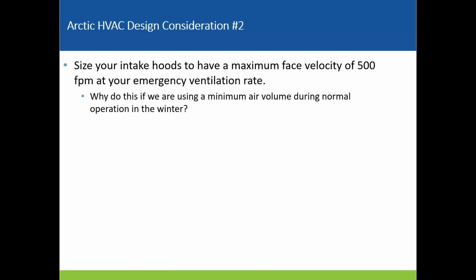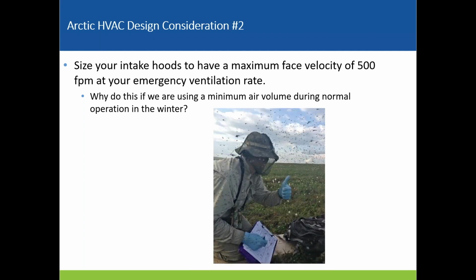So another Arctic design consideration, size your intake hoods to have a maximum face velocity of 500 feet per minute at your emergency ventilation rate. I get asked a lot, we're only bringing in 4 air changes per hour, why don't we size our hoods for just that instead of the full ventilation rate? The reason is because in the summer, when we go to cooling, we are undersized. Those are all mosquitoes. We're going to pull all sorts of crap in here. Filters.